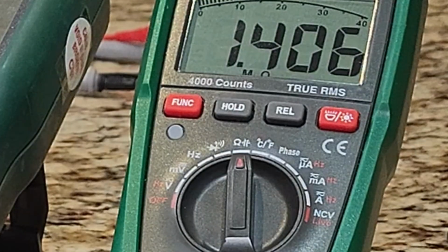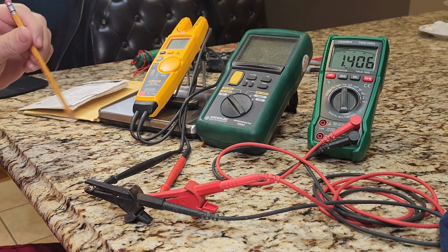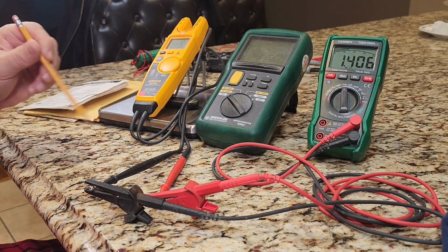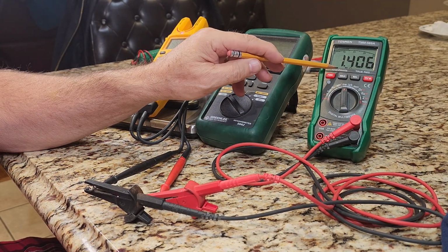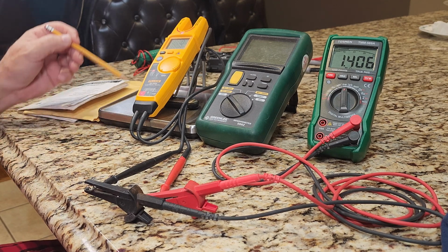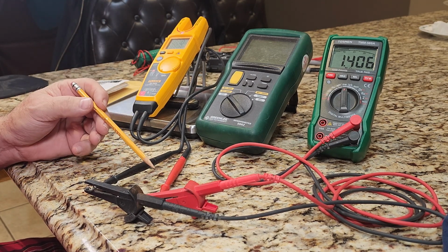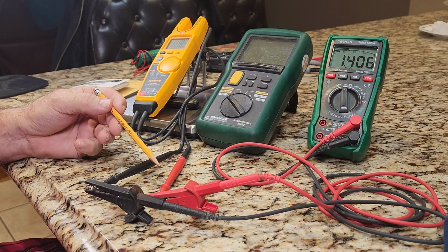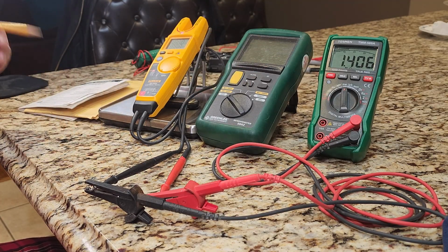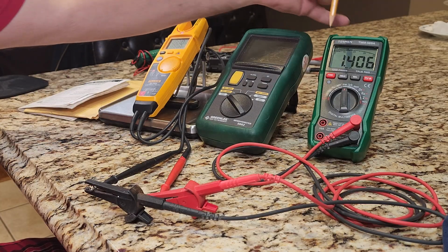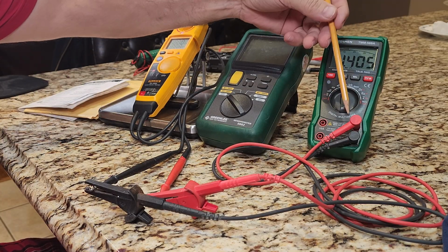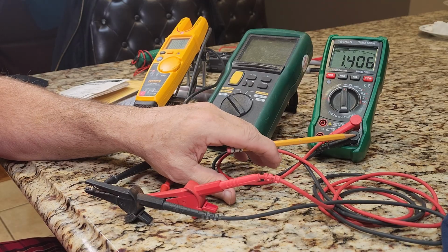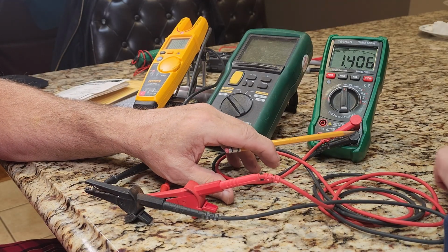Now, what I'm actually reading is 1.4 million ohms. 1.4 million? Yeah, see the M? 1.4 megohms running through this meter. By the time this lead goes through the circuitry and comes back out, it's actually 1.4 megohms. Now, how is it coming up with this reading? Well, it's inducing a voltage, and usually it puts the voltage out on the hot leg. Which one's the hot, like the black one?